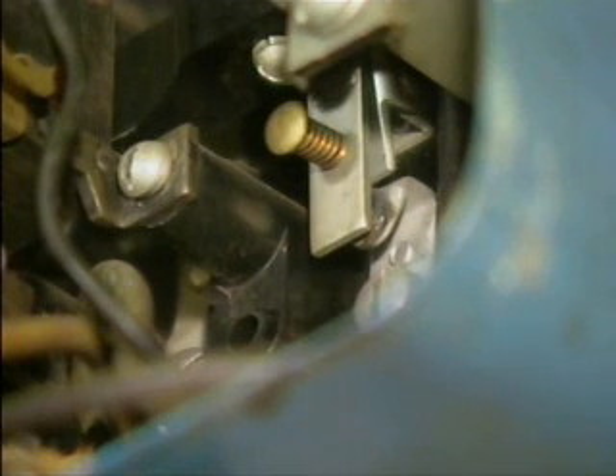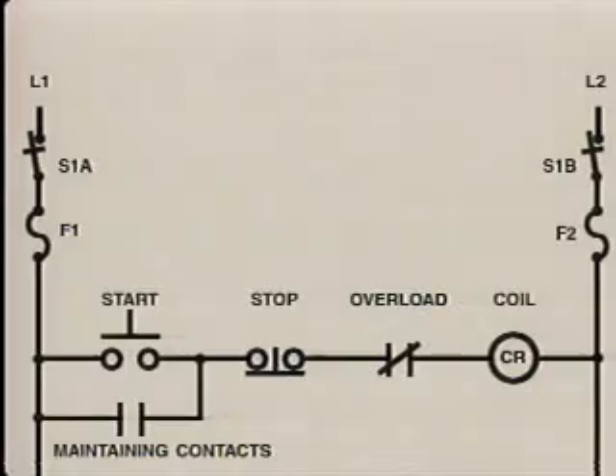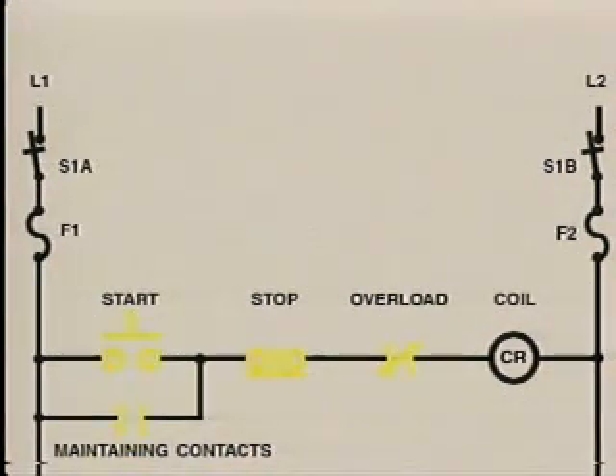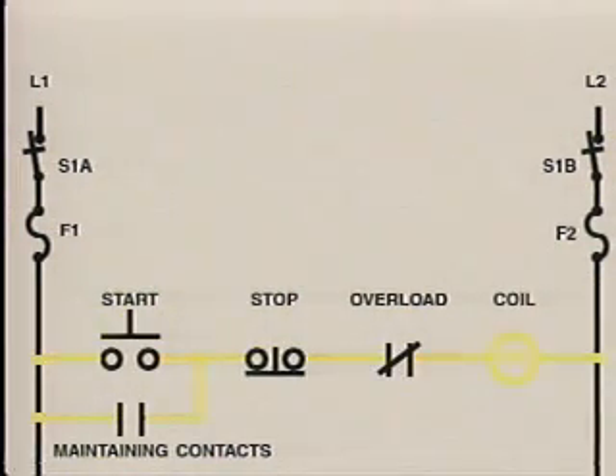So far, the electrician has seen that the coil is in good physical condition. And he has also seen that the overload contacts are in good condition and appear to be closed. However, none of these observations prove that these components are electrically sound. The electrician knows from previous experience that mechanical components, such as switches and contacts, are more likely to fail than electrical components, such as wiring or a coil.